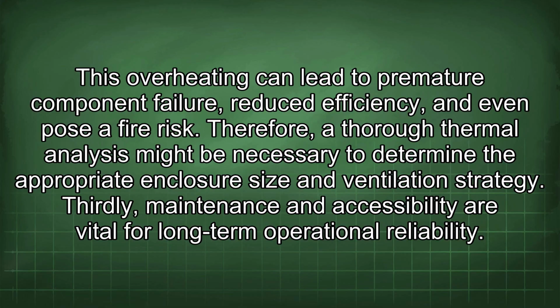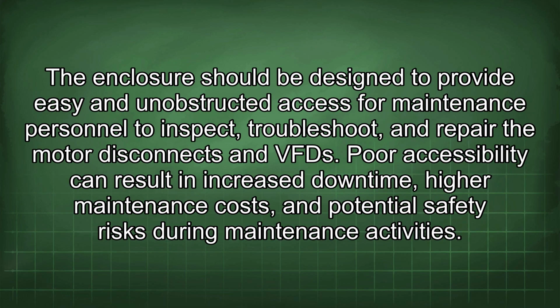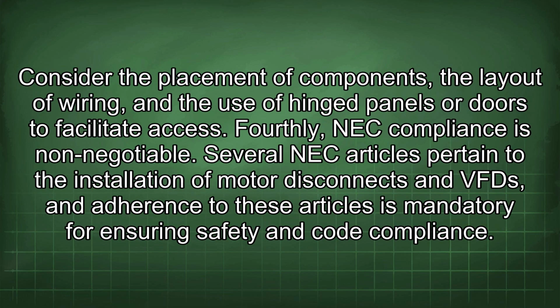Thirdly, maintenance and accessibility are vital for long-term operational reliability. The enclosure should be designed to provide easy and unobstructed access for maintenance personnel to inspect, troubleshoot, and repair the motor disconnects and VFD. Poor accessibility can result in increased downtime, higher maintenance costs, and potential safety risks during maintenance activities. Consider the placement of components, the layout of wiring, and the use of hinged panels or doors to facilitate access. Fourthly, NEC compliance is non-negotiable.